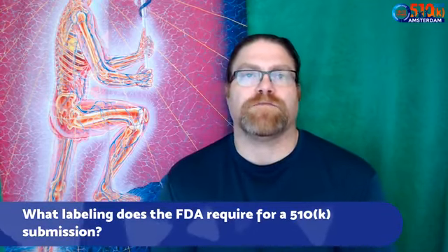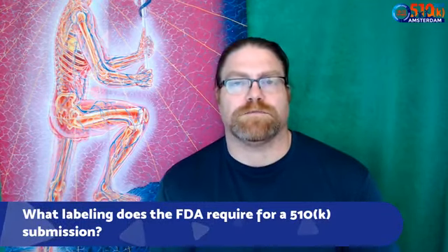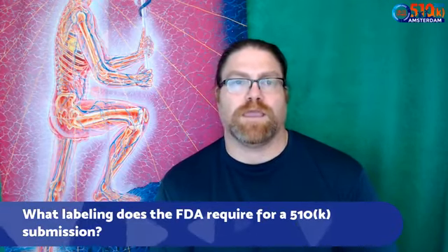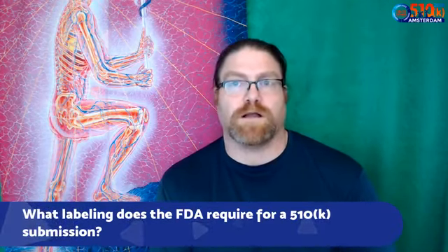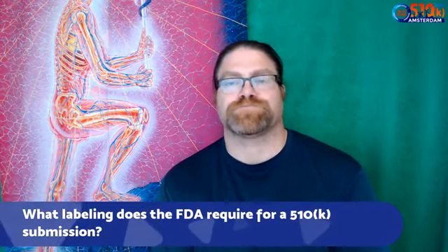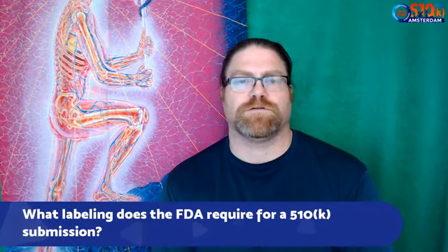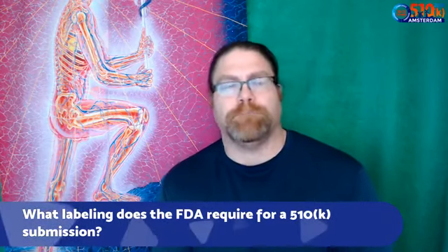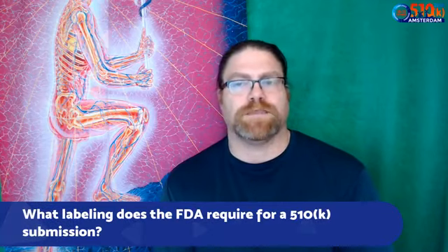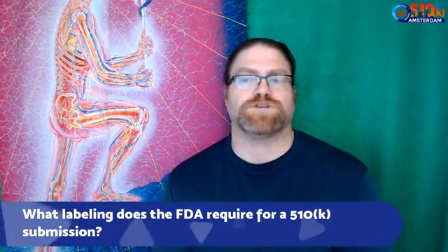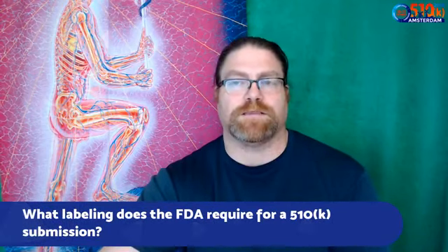And number two, you have to have the statement in there for a prescription device that this is prescription only and can, according to U.S. law, only be ordered by a physician. So those are two of the unique things that are required by the FDA. But otherwise, a lot of companies can do that. But I often find a few problems in the labeling, so it's worth reviewing with a checklist before you begin planning on submitting it to the FDA.